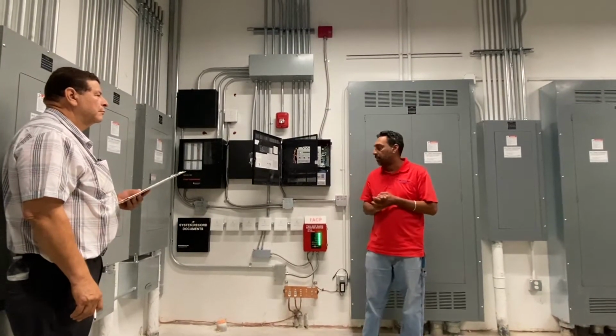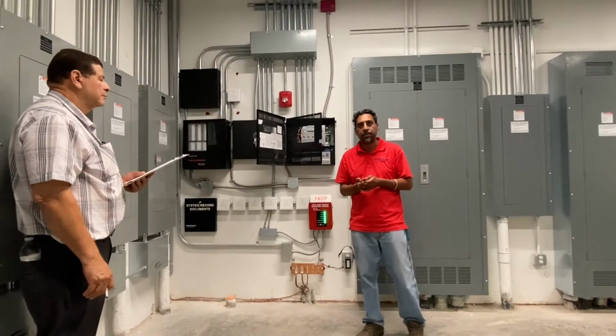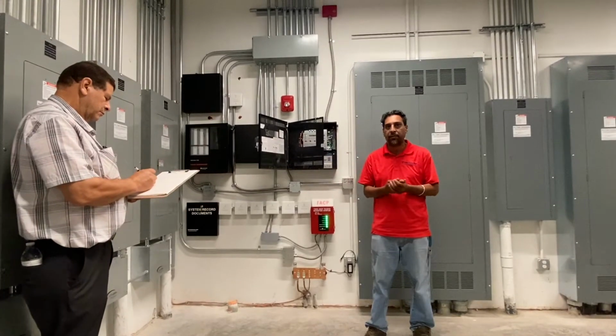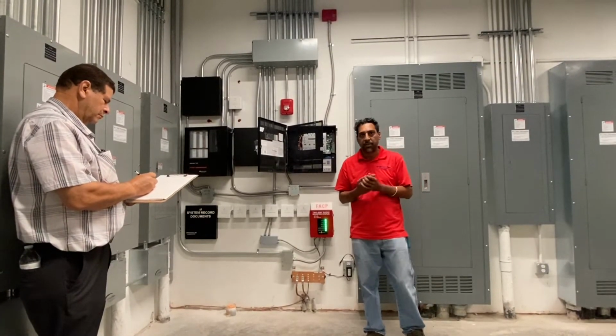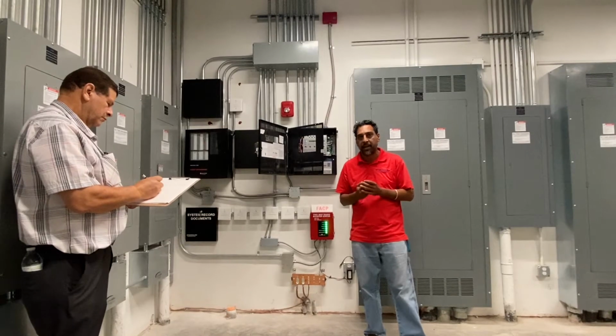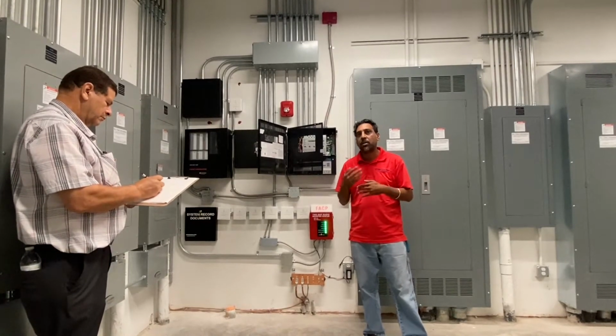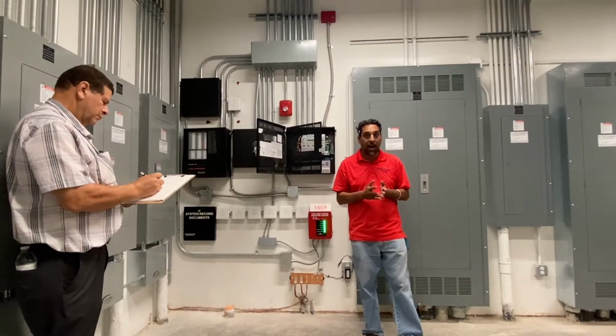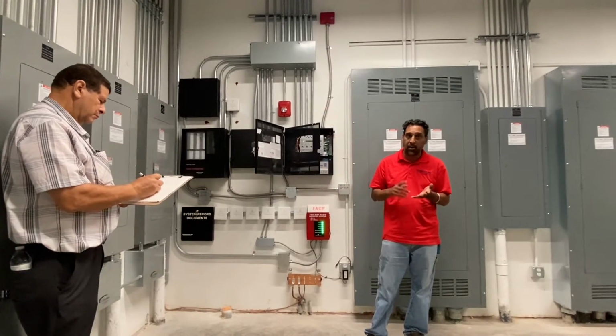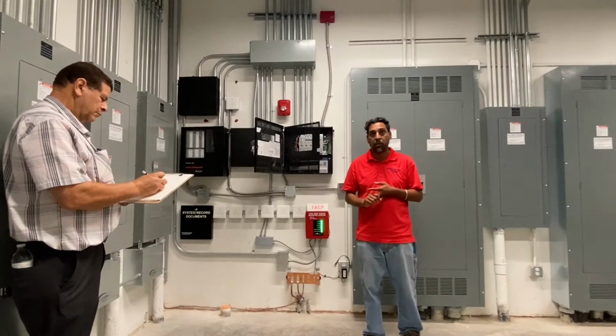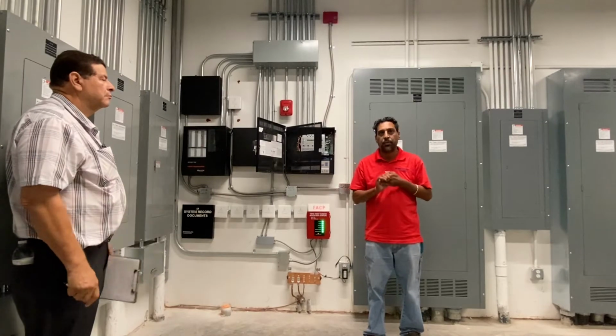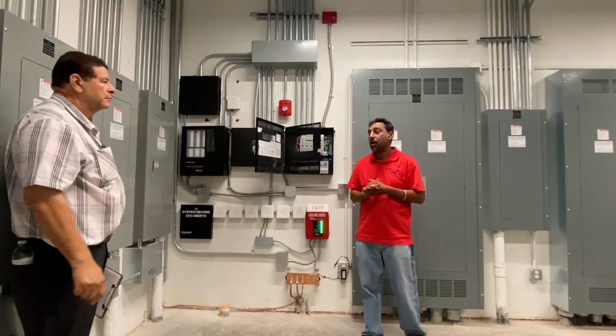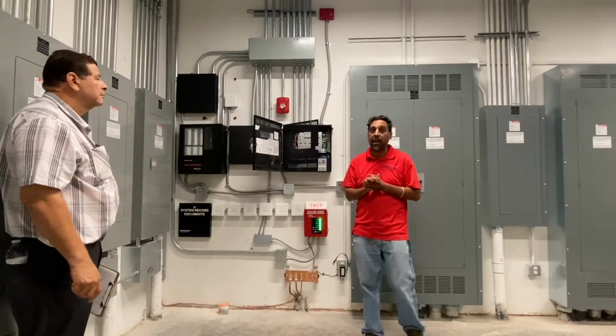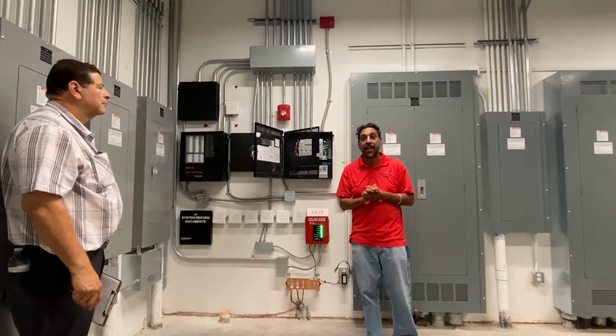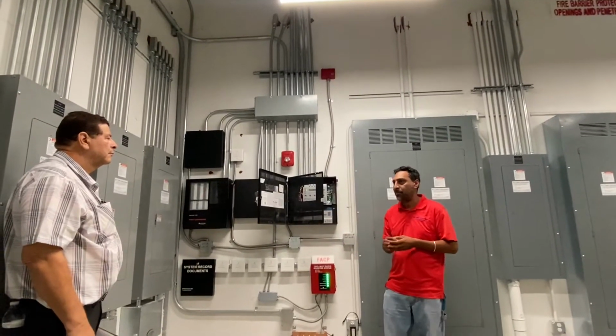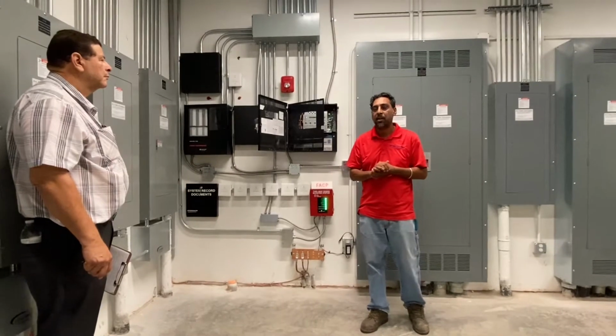You have three things on your fire alarm systems. You have your troubles, your supervisories, and your full-fledged alarms. Your troubles and supervisories do not dispatch fire trucks. They will just call who's on the list. Your fire alarms, any fire alarm, your pull station, your water flow, your smoke detectors, all of those will dispatch the fire department. We did install one of our DMP radios, which actually reports in seconds. So by the time you get here and shut it off, trucks are coming.